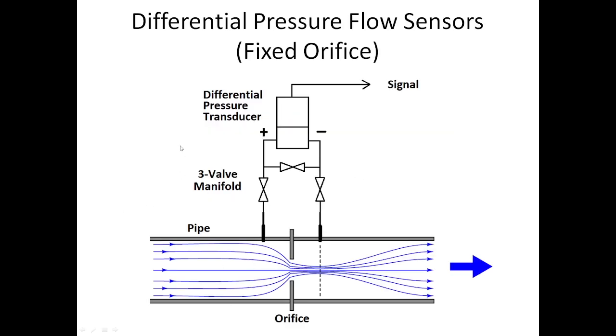All right, so let's go through the main technologies behind flow sensors. The first one we're going to talk about is called differential pressure flow sensors. There's all sorts of different types of differential pressure flow sensors. The reason they call them that is because there's always some sort of occlusion in the middle, and they measure the difference of pressure between one side and the other. Now, as we already said, Bernoulli's principle applies to all of these, and that means that as gases speed up, they create a lower pressure zone.